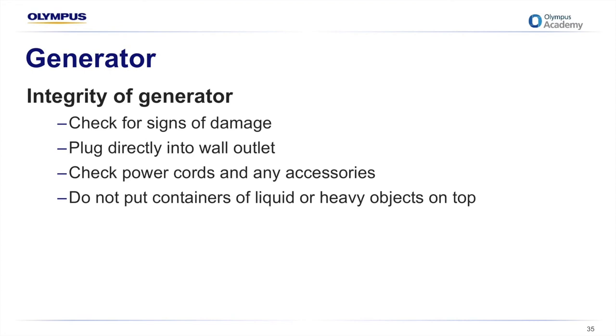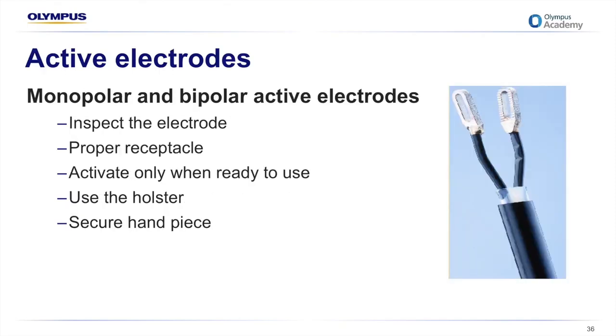Never put heavy objects or containers of fluid on top of a generator. Fluid and electricity are a dangerous combination. Most generators today have electronic components that might be damaged if something heavy is put on top of the generator also. Safety measures regarding monopolar and bipolar active electrodes involve inspecting the active electrode for damage before use, including the insulation cord and handpiece. Never let anyone force a connector into the generator. This is a clue that the instrument is not meant to be used with that generator.